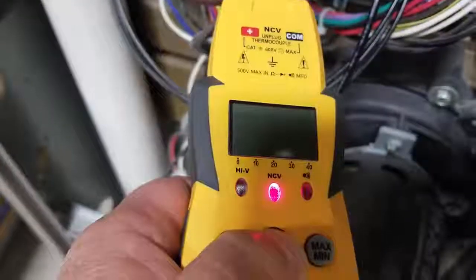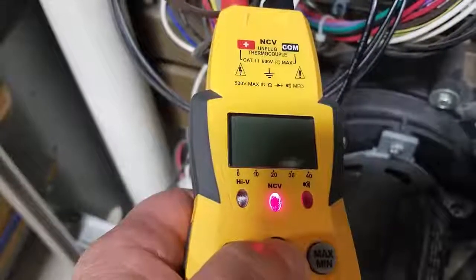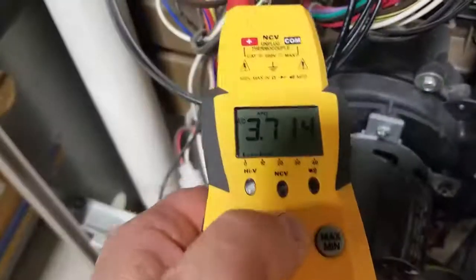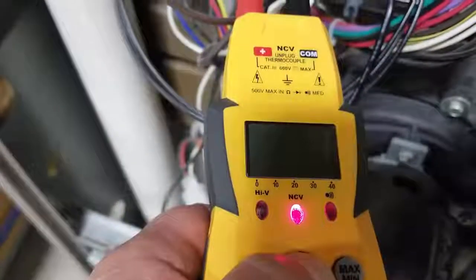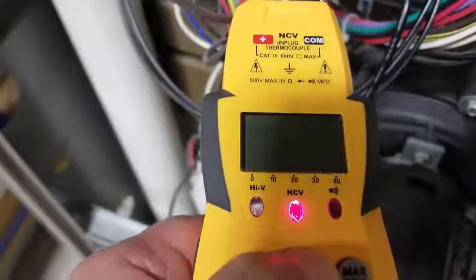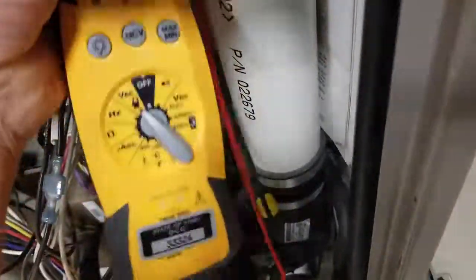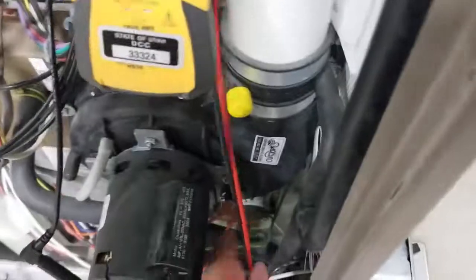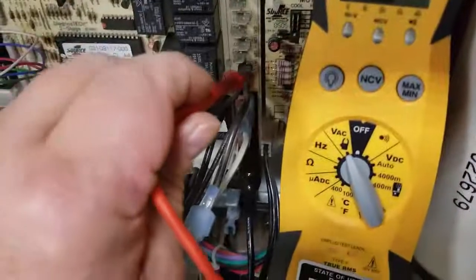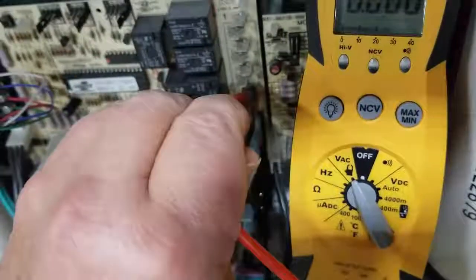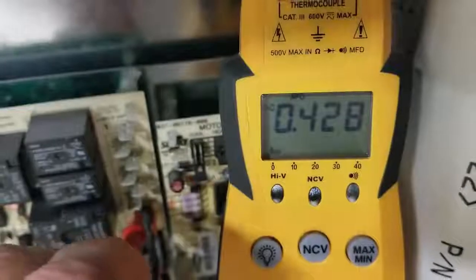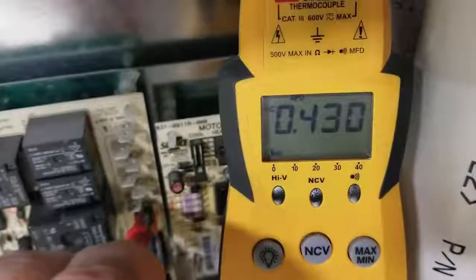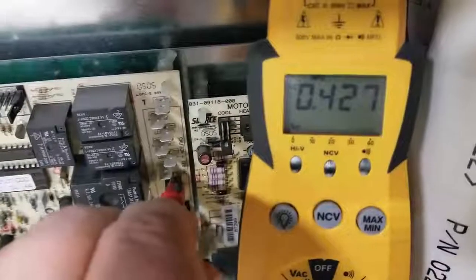And if I only use that for checking main power to the furnace, I'm operating under the assumption that I've got 120 volts to the furnace. The meter's telling me there's power there. Well, the reality of it is this. There's still power there. It's just that the neutral side is gone or disconnected, and it's not 120 volts. It's significantly less than 1 volt. So this furnace will never start and run.